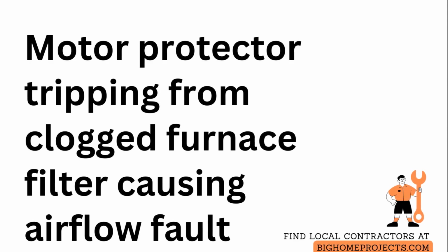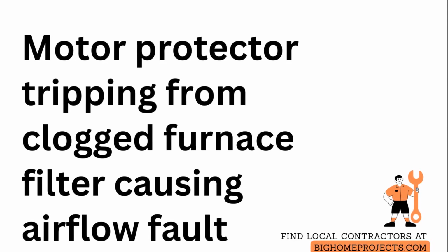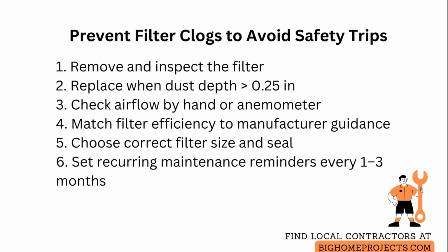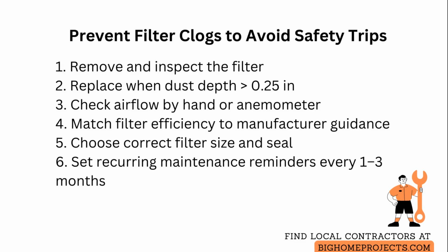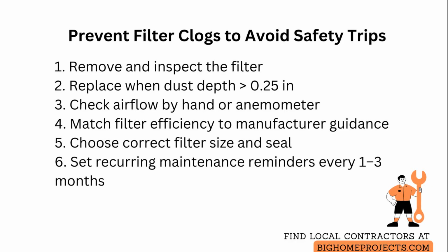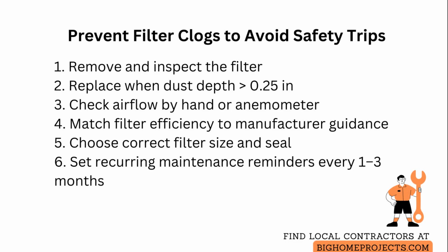Can dirty system air filters cause safety switch activation by restricting airflow enough to trigger an overheat or pressure fault? When an air handler or furnace filter becomes clogged, the blower has to work harder to move air, which raises motor temperature and can cause the internal motor protector or a thermal safety switch to trip.